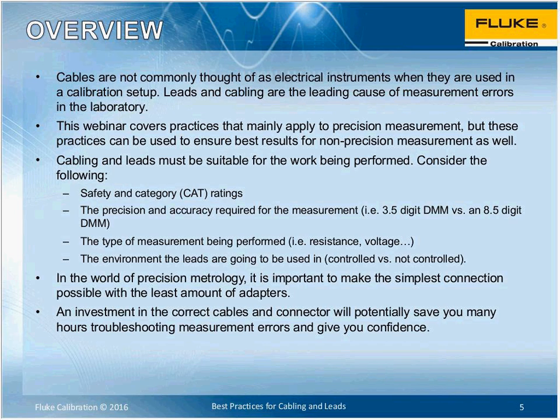being performed. What you'll note today from this webinar is that when you get into the precision measurements of resistance versus voltage, there are some differences that can result in large PPM errors between measurements if the wrong cabling is used. And also the environment the leads are going to be used in. Is it a controlled environment? Are there a lot of outside influences, such as magnetic fields, electrostatic fields, for instance? We'll discuss that today.